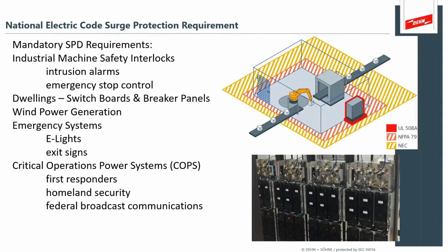And the National Electrical Code has some pretty clear guidelines on where you have mandatory requirements as opposed to suggested, informative ones. So the normative requirements fall into human safety areas where you've got industrial machine interlocks, and it also applies to dwelling switchboards, breaker panels. You see it mandated in the wind generation industries because of the risk of fire; direct strike lightning on these generators is a big deal. Emergency systems, in fact, all your e-lighting, exit sign type power panels all have to have SPD installed on them to protect those systems critically.